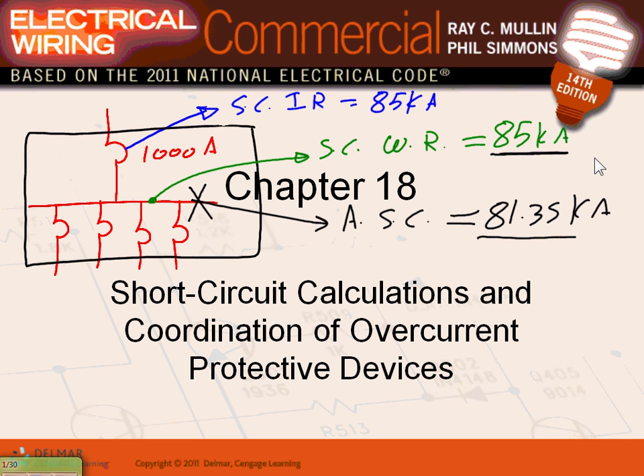The relationship between these values is usually that the 85 kiloamp must be more or equal to the 85 kiloamp, and the last one, the red, also must be more or equal to the 81.35. Make sense? This value must be more or equal to this value, and this value must be more or equal to this value. Or equal, remember the equal. Any question about these three values? Interrupting rating for circuit breaker, withstand for the panel, and short circuit. If you grab the three phases together, bolt them together, and flip the switch.